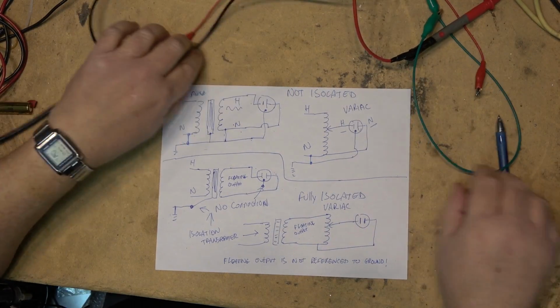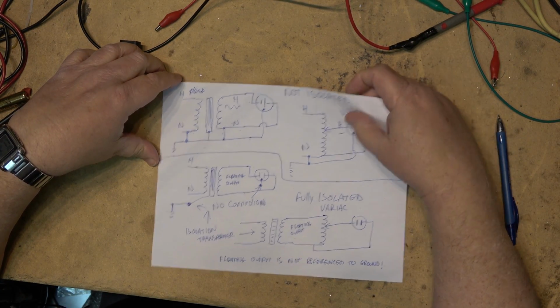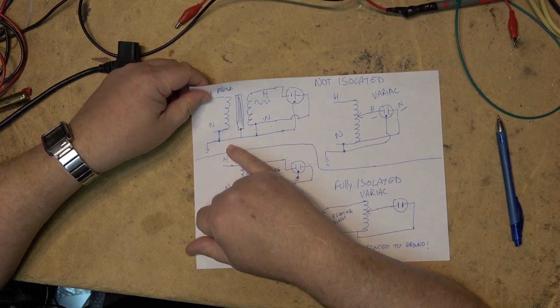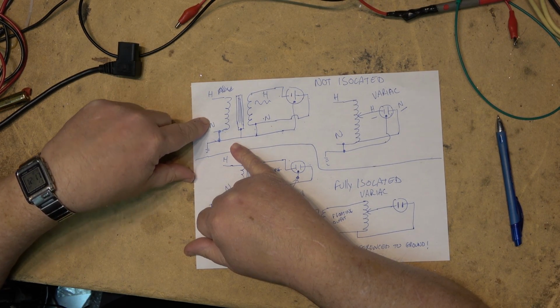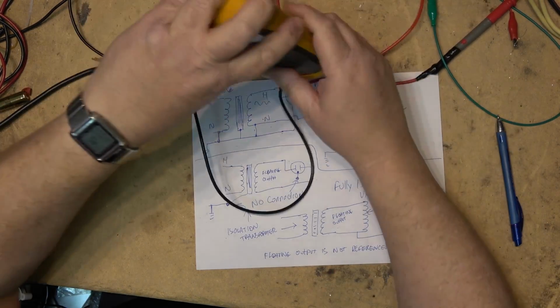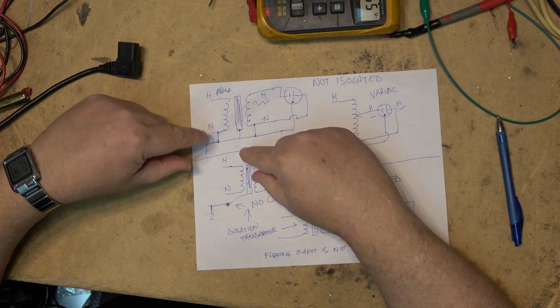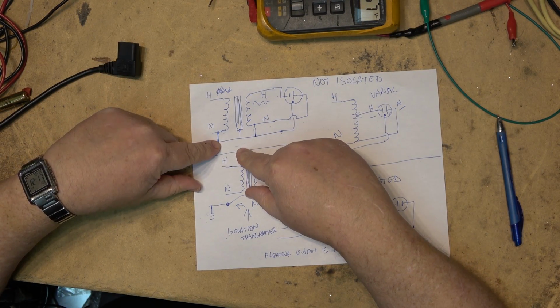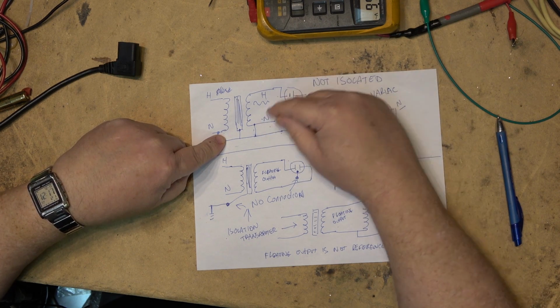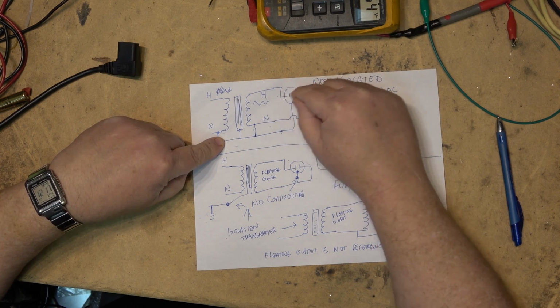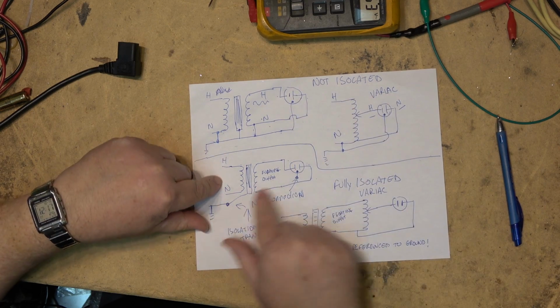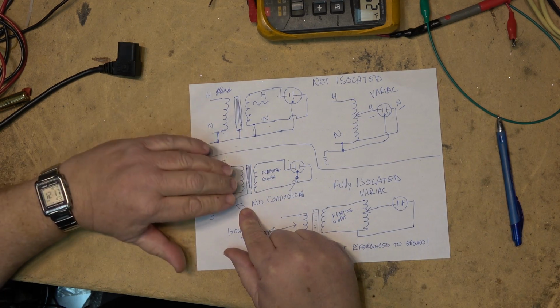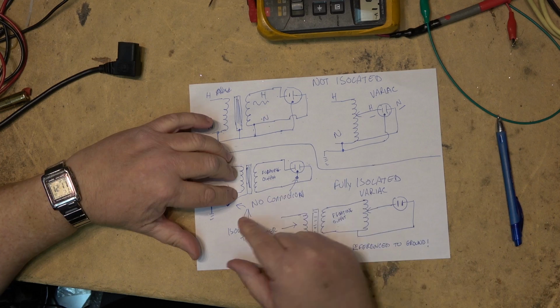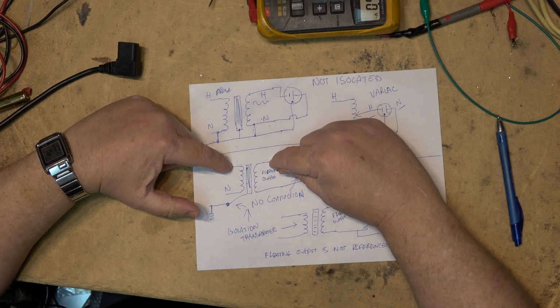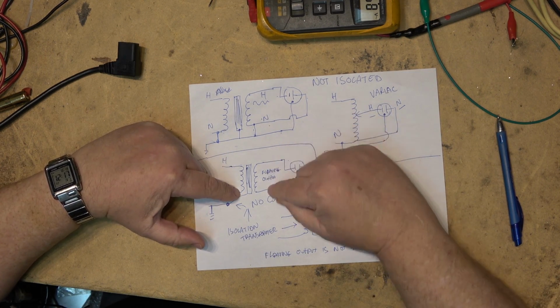To have a fully isolated isolation transformer, there can be no reference to ground or neutral. If you buy an isolation transformer and you put your meter in ohms mode, and attach it to the ground prong or the neutral prong, and go to the output, there should be an infinite reading between everything, because there is no connection. There's no connection between the hot and neutral and the output. So between here and here is infinite reading. Between there and either of these, it's infinite reading.